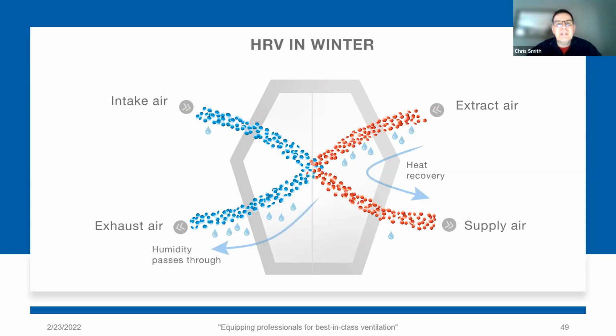So we're looking for the HRV to help manage energy transfer between these two airstreams, and that's exactly what it does. The heat from inside the building is transferred from the extract air through the heat recovery core into the supply air and then re-delivered back to the house. However, the air itself is kept distinct so that the exhaust air is delivered outside and the fresh outdoor air is delivered inside. The result is a comfortable indoor air supply temperature. Notice that in winter, your indoor air is typically going to be more humid than the outdoor air. Notice that with an HRV, there's no humidity transfer. And so the exhaust air, while it gives up its heat, it maintains the moisture. And so the moisture in the extract air is exhausted to the outside.